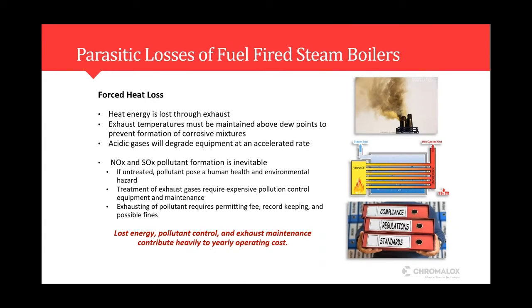Moving on, when you look at parasitic losses, again, just because you've combusted that fuel source into heat doesn't mean that that heat is being used in your process. So for fossil fuel systems, we know that after that combustion, a percentage of that heat is just lost right to the flue. So it's not doing your process any good. So you're spending money and energy to convert that to heat, but really all you're doing is sending it right out to the environment. So that's what we're considering a parasitic loss, is basically it's not doing you any good, even though you're using energy and using resources to create that heat.